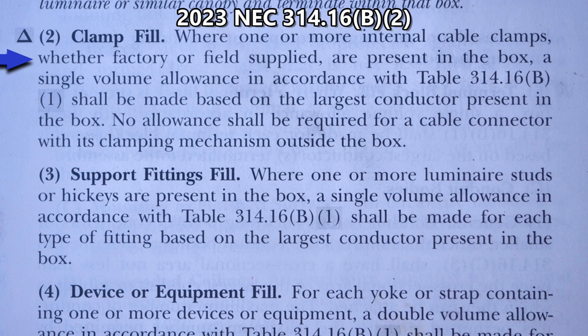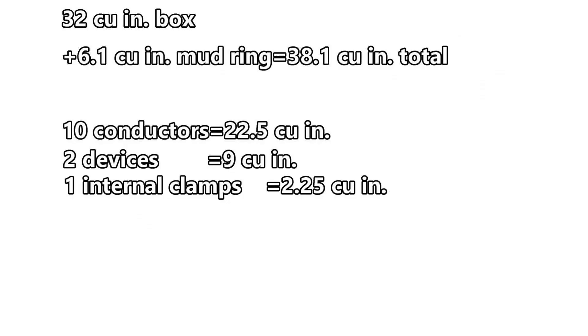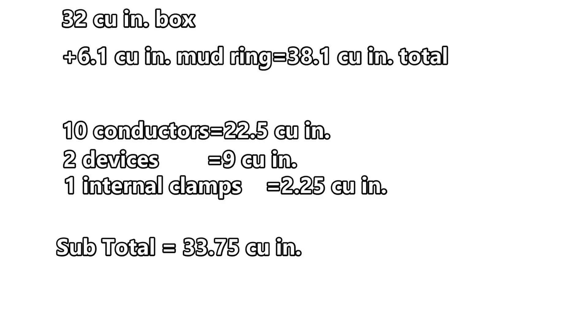Here we are at NEC 314.16B2, clamp fill. Where one or more internal cable clamps, whether factory or field supplied, are present in the box, a single volume allowance in accordance with table 314.16B1 shall be made based on the largest conductor present in the box. No allowance shall be required for a cable connector with its clamping mechanism outside the box. So we'll add one volume allowance for the internal clamps, which is 2.25 cubic inches, giving us a subtotal of 33.75 cubic inches.